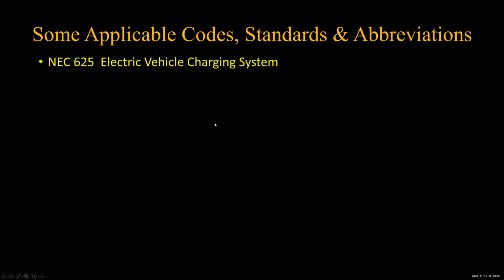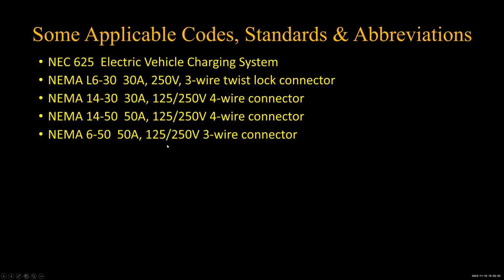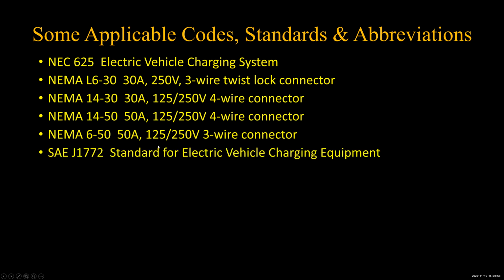Okay, NEC 625 talks about the different kinds of connectors. And this is the big one here, the SAE J1772. That's the one you've been seeing pictures of all over, and it's pretty well standardized now. That same plug will work on either 240, 208, or 120 volts. The plug itself, plugging into the car, the front end where the plug is, and the isolation transformer and so forth, that has to be set up for the particular charging current.